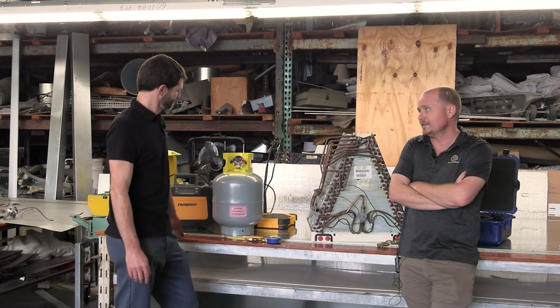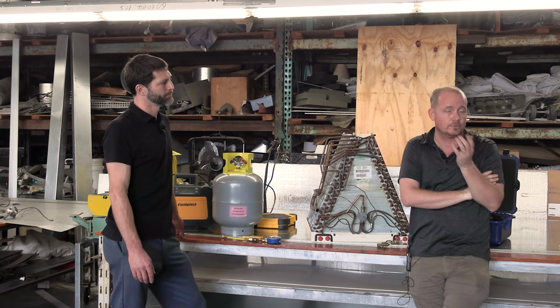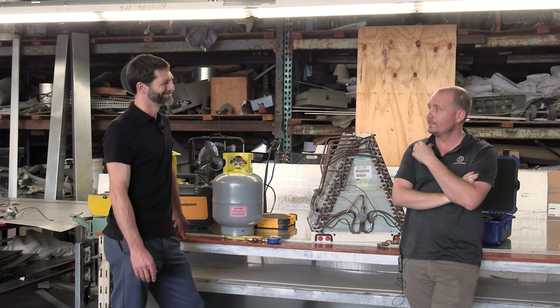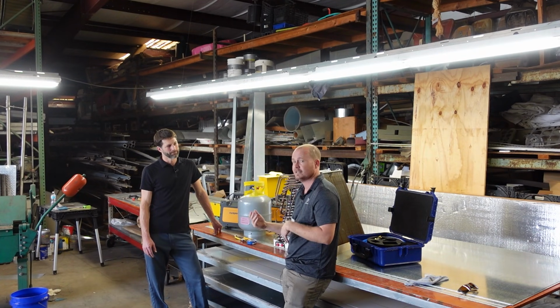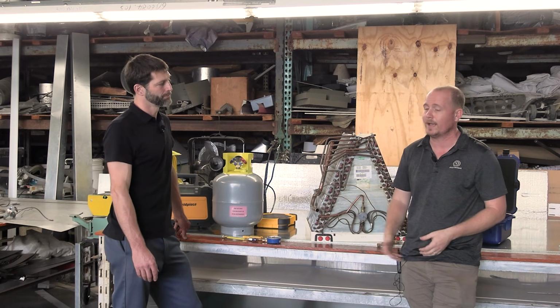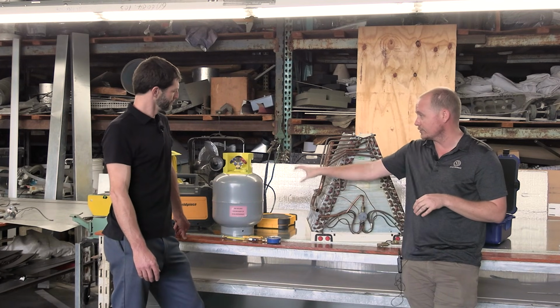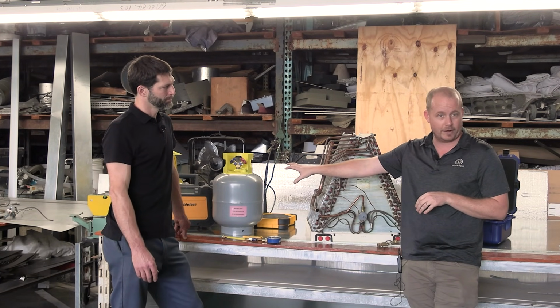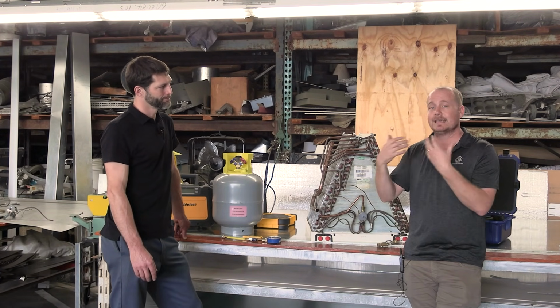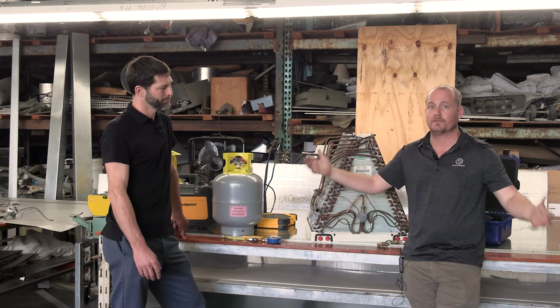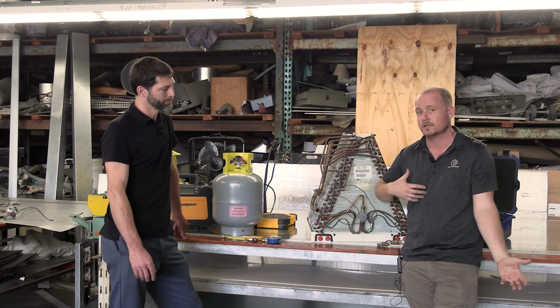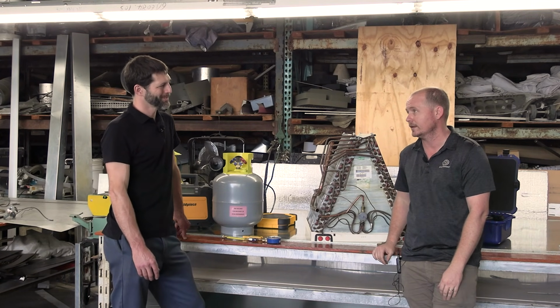And that also increases compliance, too. If you have the proper tools, and I'm talking to your contractors out there, if you have the proper tools and you have the proper practices, it's going to be much easier to do things the right way. But always, always, always make sure that you're using a scale, make sure that you're not filling above 80%, and keep refrigerant uncontaminated. Keep it from being mixed, keep air from getting into the system, and if you do all those things, I think you're going to get a pretty good result.